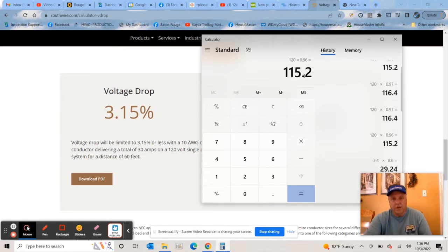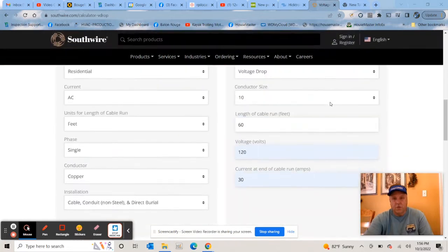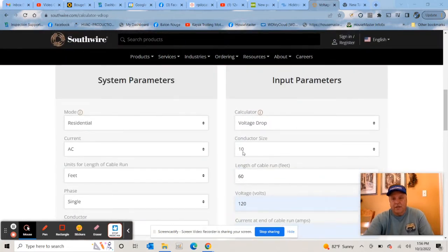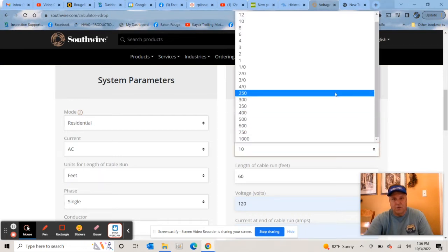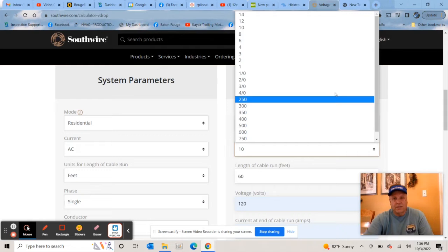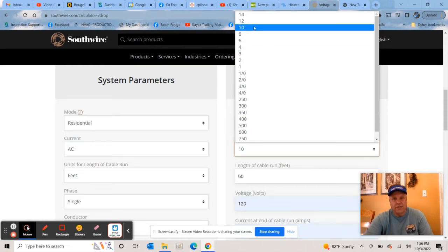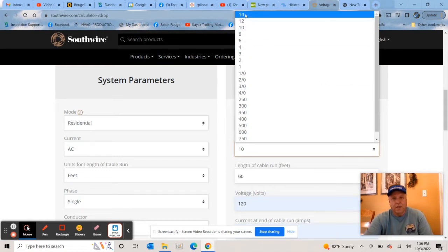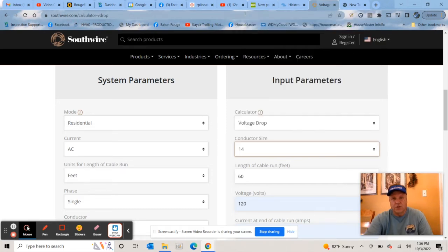This is how we figured out that we're not doing anything dumb by running 75 feet of cord, because if you run a whole lot of cord, you can do something very dumb. So for instance, if instead of having that 10 gauge cord, your average extension cord is only about 16 gauge, which it doesn't even give us. It gives us a 14 gauge. So that would be probably a medium size, your regular 3-prong outlet extension cord.